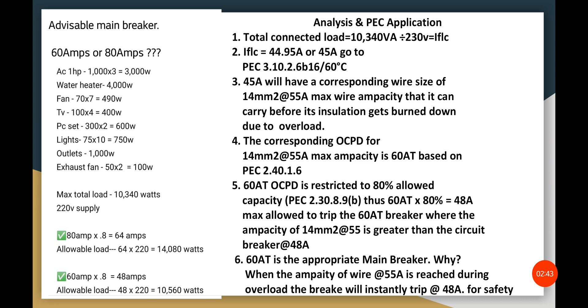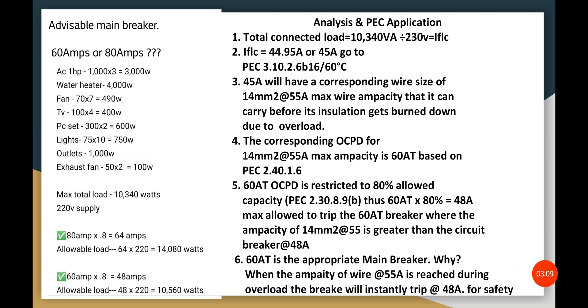First, the total maximum connected load is 10,340 VA. When we divide that by 230V, we get the full load current. The full load current comes out to 44.9 amperes. Based on the rounding rules — if the decimal point is more than 0.5, round up; but here it is less than 0.5 — so we use 44 amperes. However, we will round up to 45 amperes for our selection.